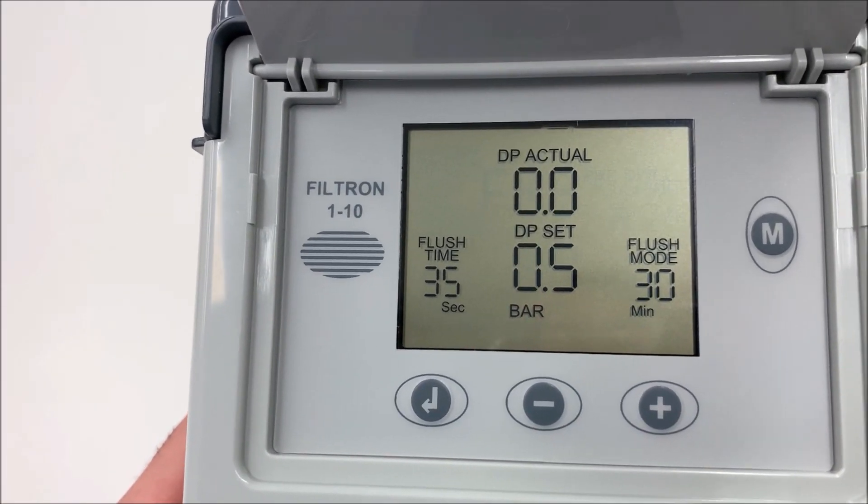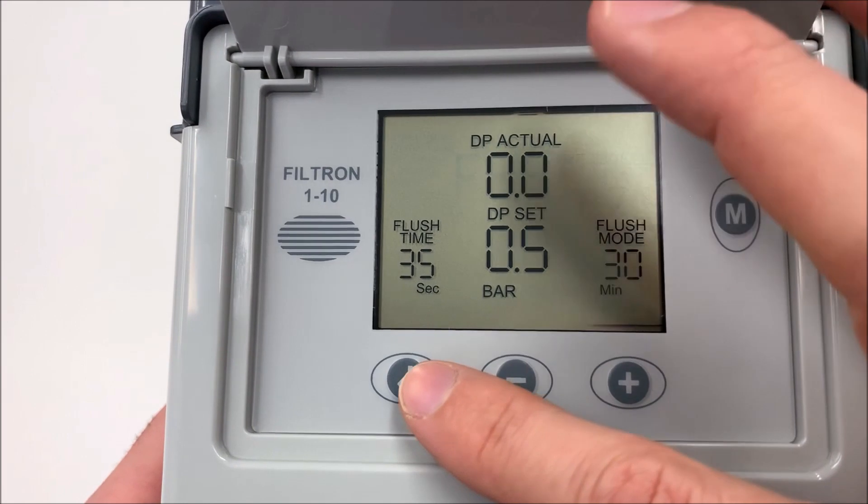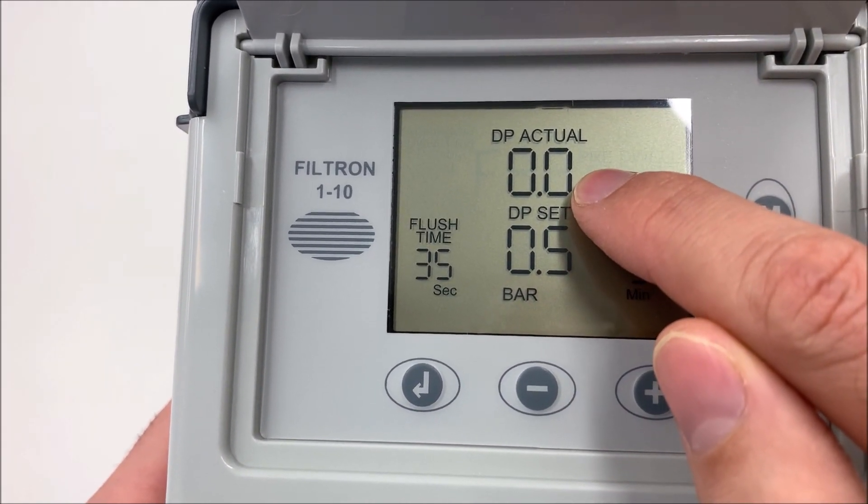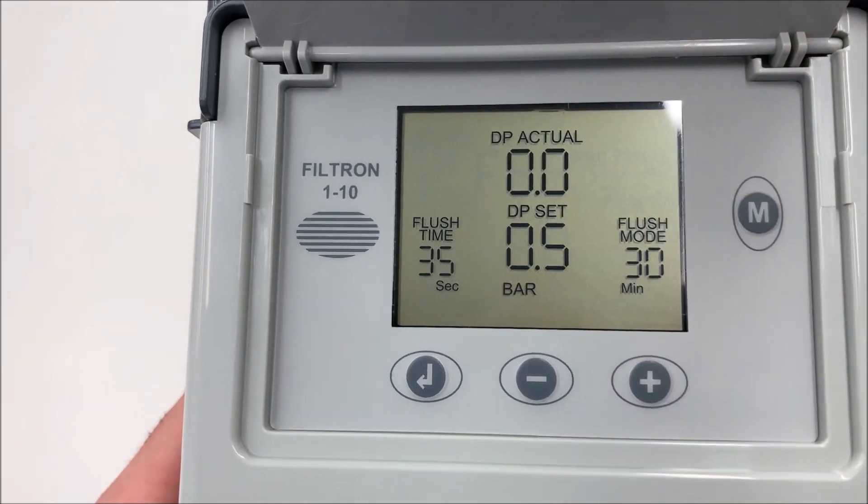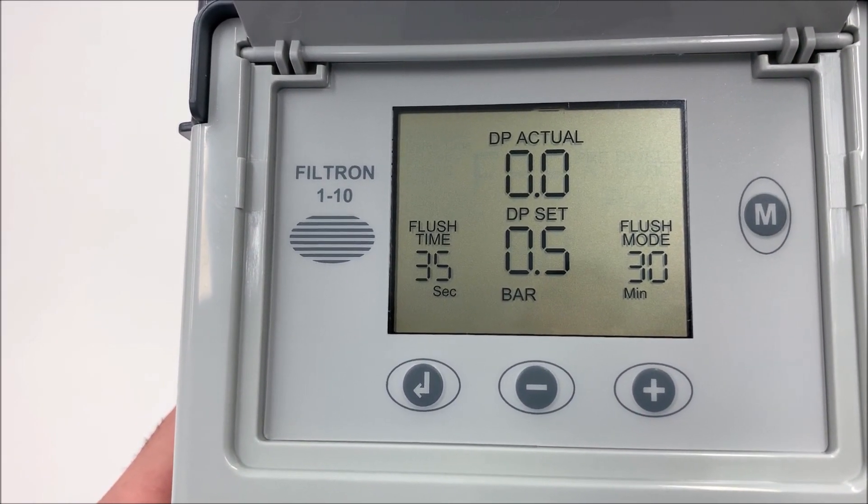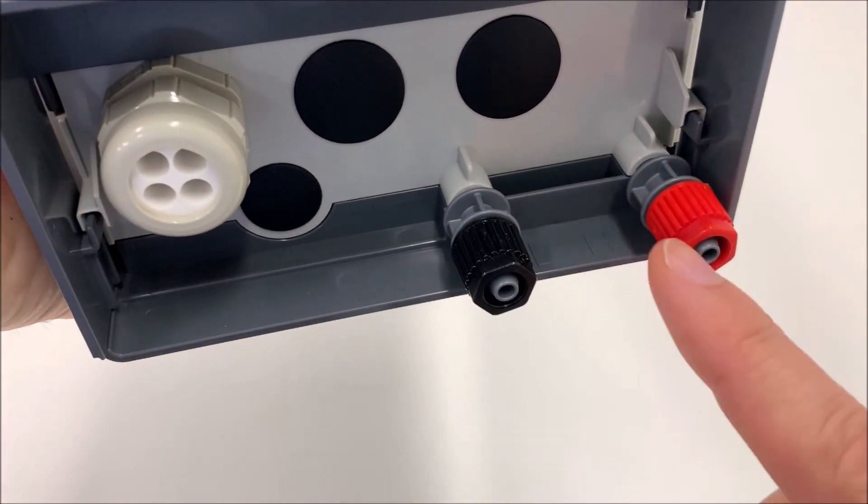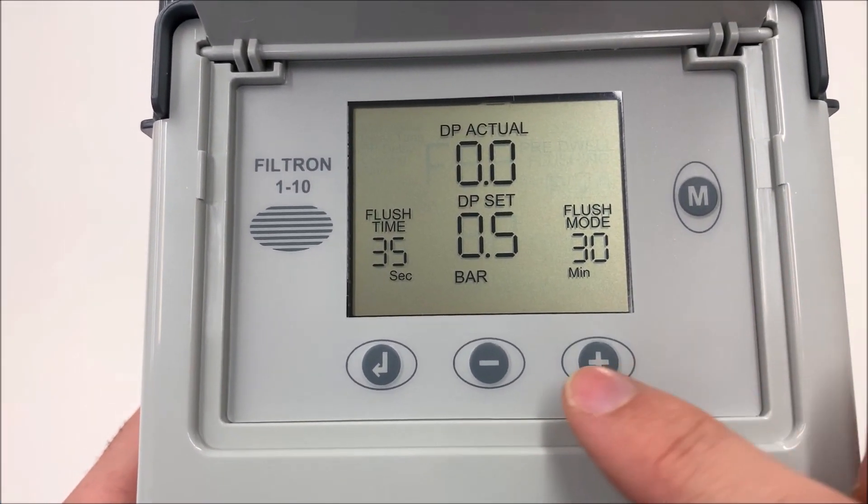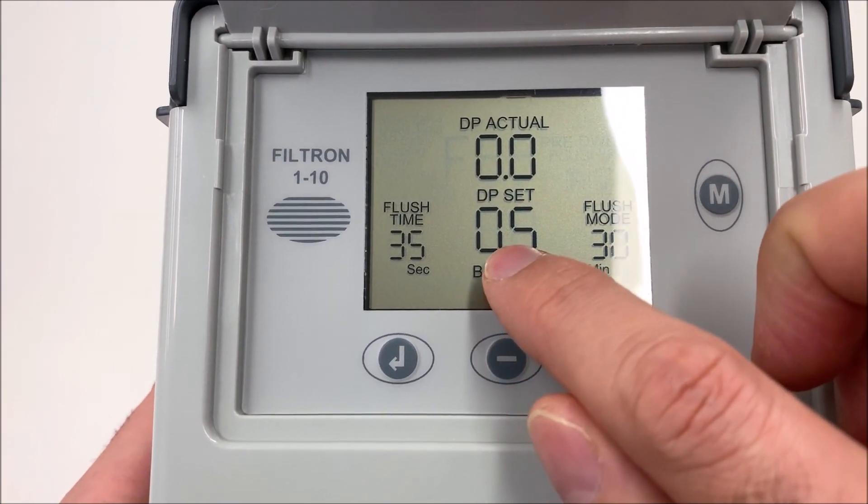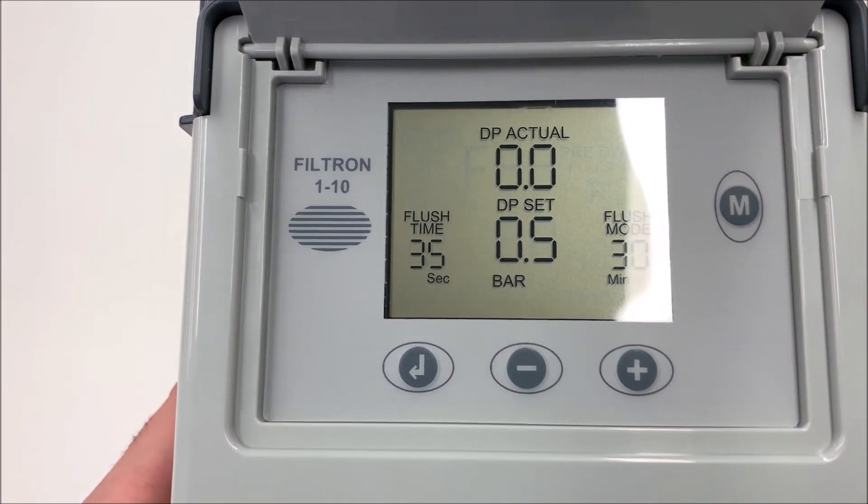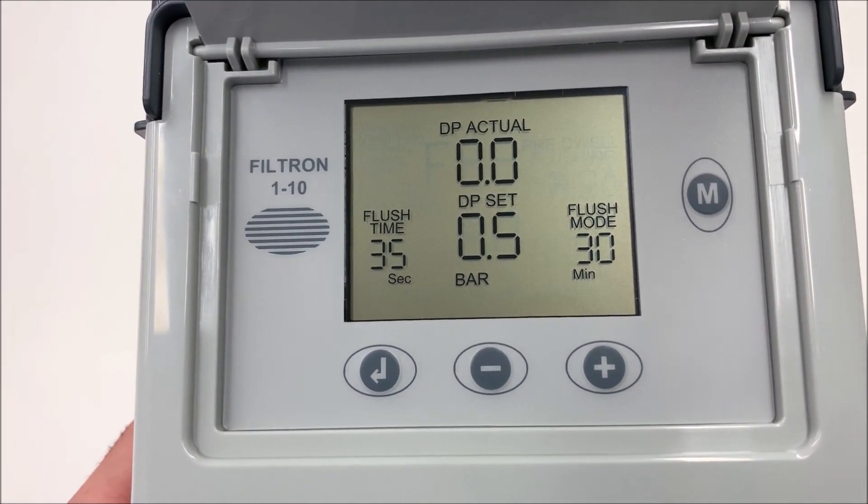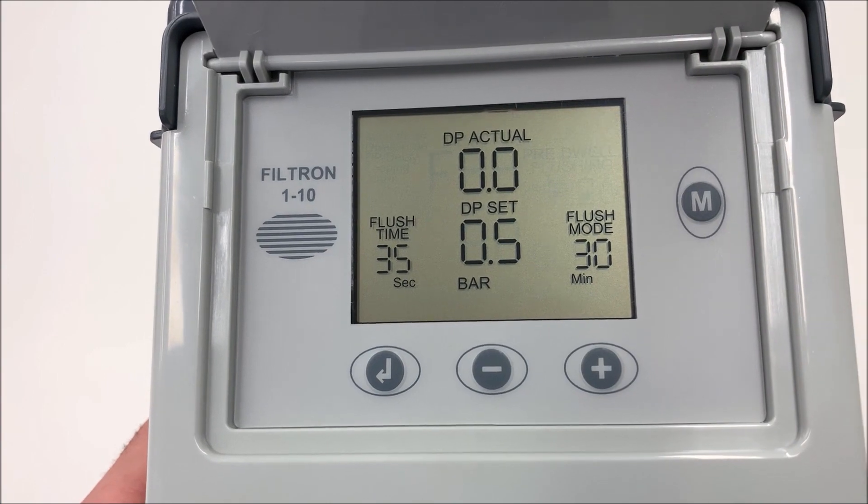We will see now how to manage all the buttons on the screen here. The first thing you will see here is the DP actual, the current differential pressure. Our differential pressure manometer is reading. The second thing is the preset DP value. In that case is 0.5. That means that when we arrive to 0.5 bar differential pressure, the controller will start the backwash.